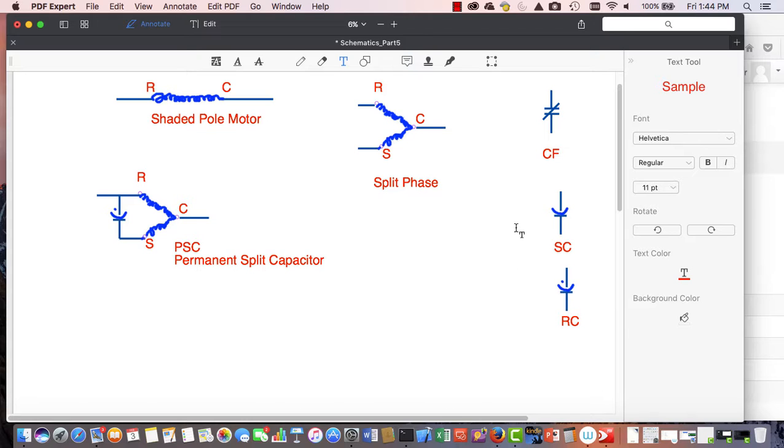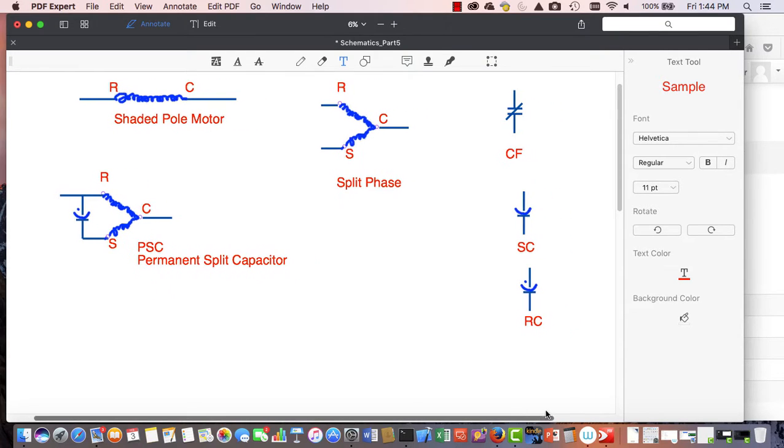Okay, so a start capacitor has a higher capacitance. The run cap, as you might have remembered from class, has a capacitance between 5 and 60 microfarad. The start cap comes up from 60 and can go on up. So I'm just going to use whatever symbol, like it can go up to 250 and so on and so forth.